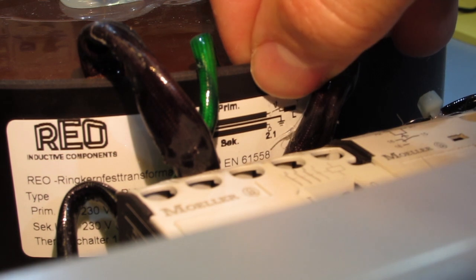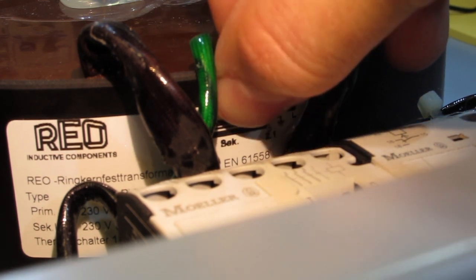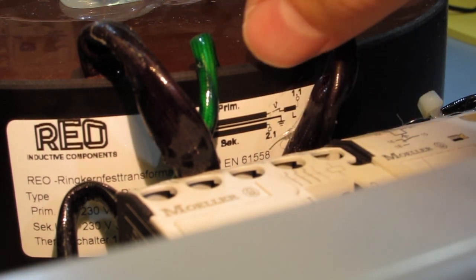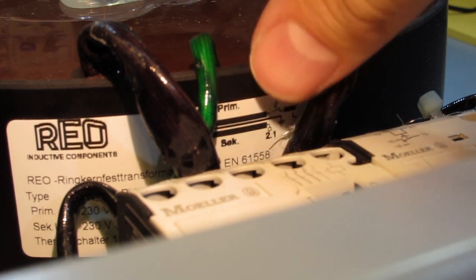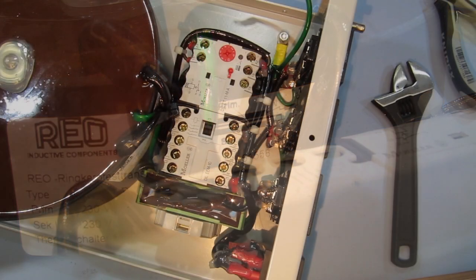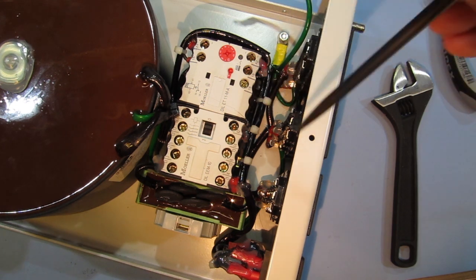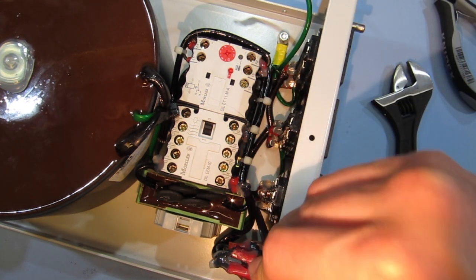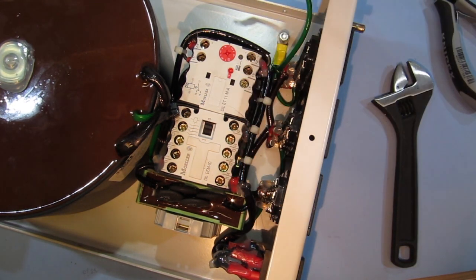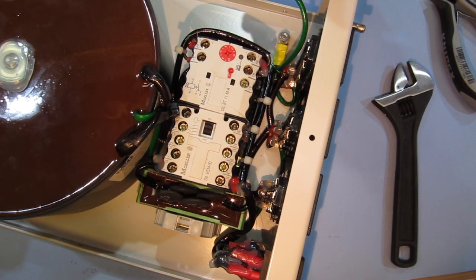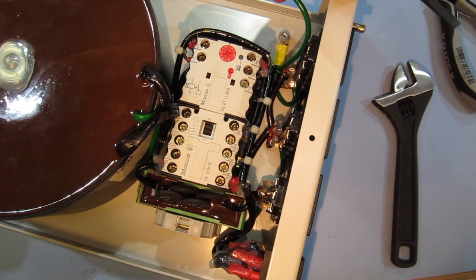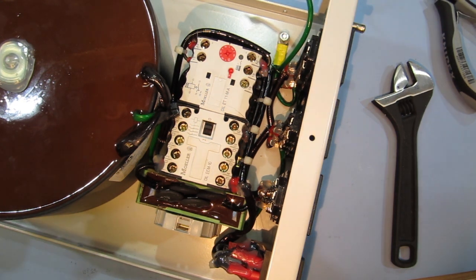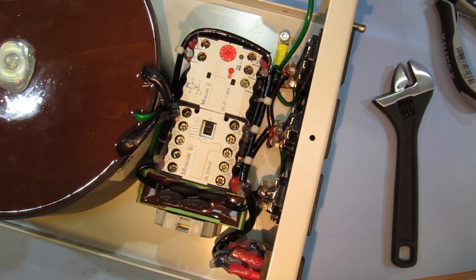And the earth is connected to a shield between primary and secondary for additional safety, so it's not connected to any windings, so we're all good there. So I think it's quite difficult to see on camera, but there is an earth wire at the bottom. It looks like they've just got normal PVC coated earth cable within a silicone kind of sheath. You'd normally do that for heat resistance, but I guess they're trying to add an extra barrier of isolation here.